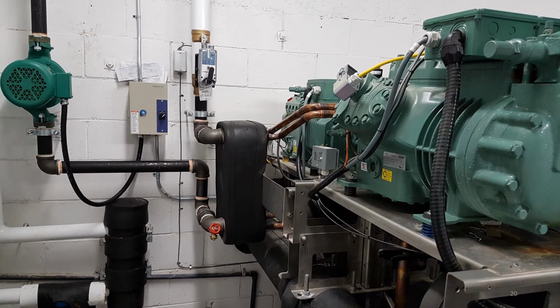Here's an example of what this looks like as a real installation. Here there are two chiller modules in this case. Both modules are connected to the cooling tower as their primary condensers. This is shown there off the photo at the bottom. And the chiller towards the back has a secondary condenser for heat recovery. In this case, this condenser is fed by the green pump, which supplies a boiler system used for domestic hot water. Domestic hot water loads are very intermittent, and this chiller has the ability to direct its hot refrigerant between the cooling tower loop and the domestic hot water loop.